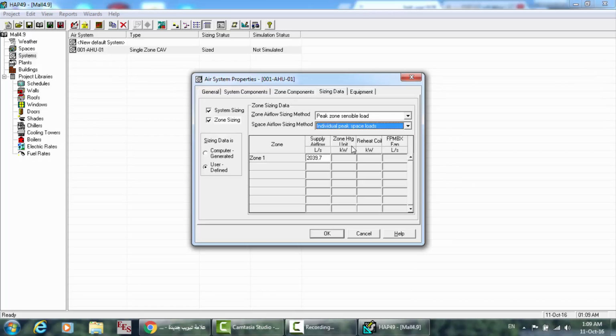And if you choose individual peak space loads, it will be calculated according to the peak zone sensible load, but it will be distributed according to the individual peak space loads. Every space has its peak. Here you may have many peaks. Okay, so according to every space peak, the flow rate will be distributed. Again, if it is coincident space loads, it's according only to the peak of the sensible load, and then HAP automatically will see the coincident space loads, and the flow rate will be calculated. So this is the coincident space loads, sensible space loads to be accurate.